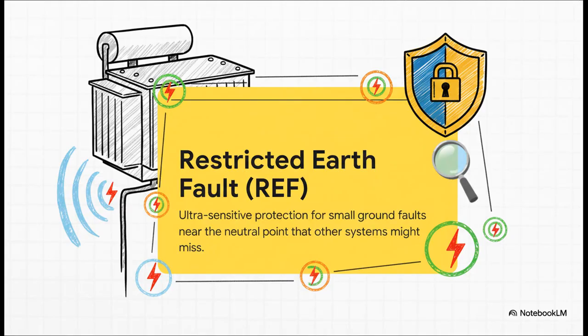So for this job, you need to bring in a specialist. It's called Restricted Earth Fault Protection, or REF. Think of it like putting a super sensitive microphone right next to that vulnerable neutral point. It's a whole separate, dedicated system that's tuned to hear even the tiniest ground faults in that one specific zone. It's an absolutely crucial layer of backup.